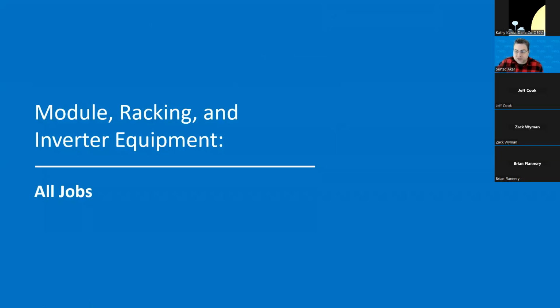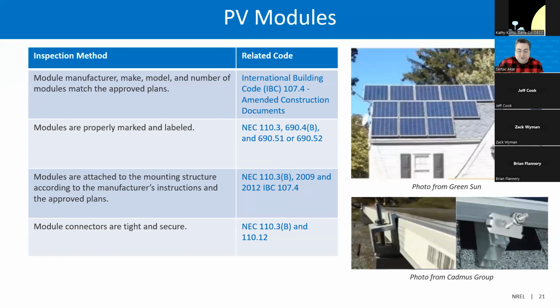Next thing to check is the module racking and the inverter equipment. The first thing is the PV module. Inspectors should verify that the module manufacturer, make, model, and number of modules match the approved plan. And modules must be properly marked and labeled, and module connectors must be tight and secure.